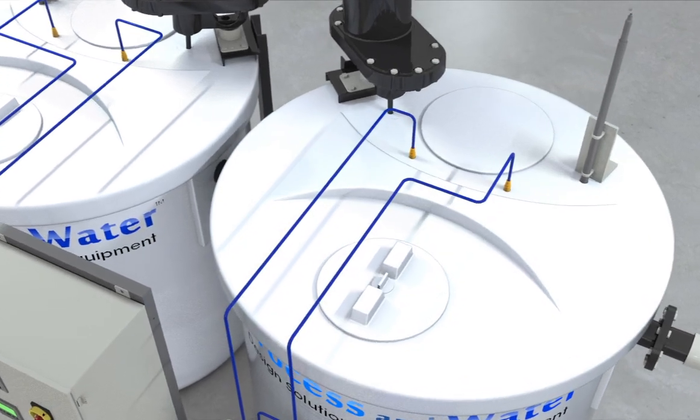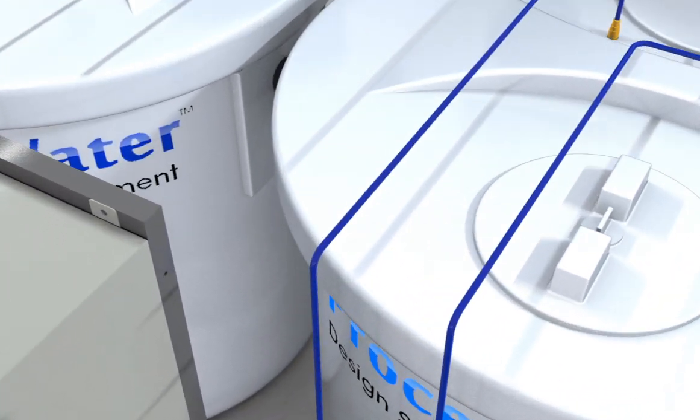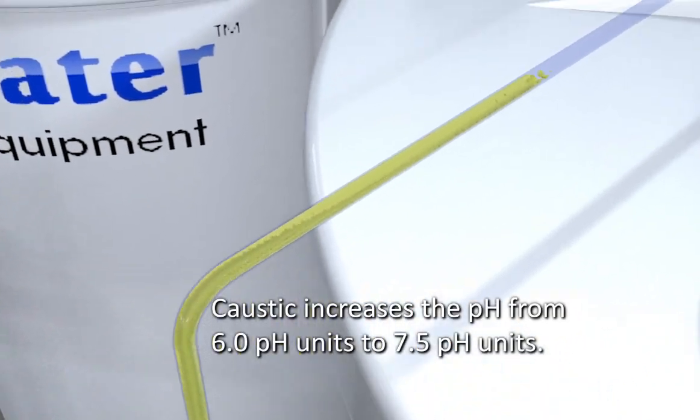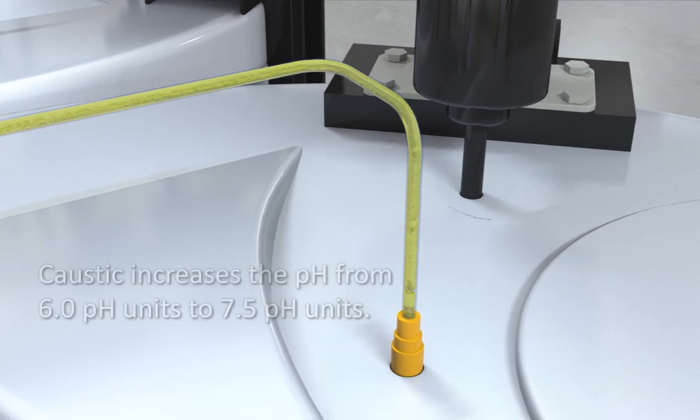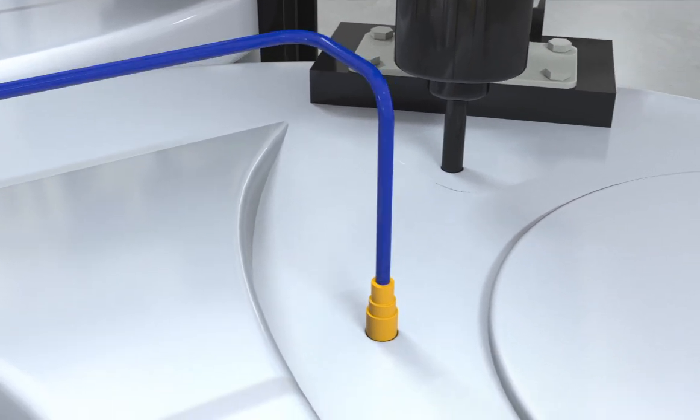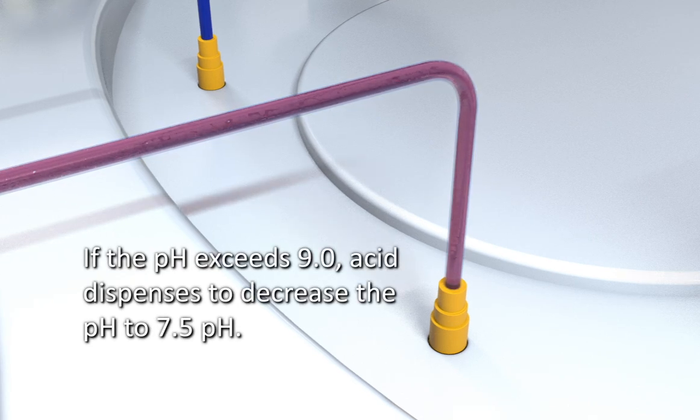The second caustic metering pump feeds the chemistry once again to increase the pH from the 6.0 pH units to 7.5 pH. If the pH should increase more than desired to over 9.0 pH units, then the acid pump feeding this tank will feed acid to decrease the pH to 7.5 pH units.